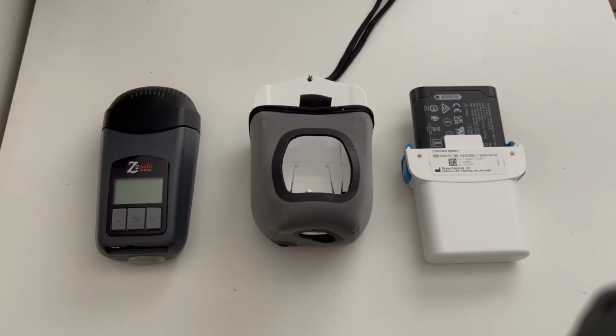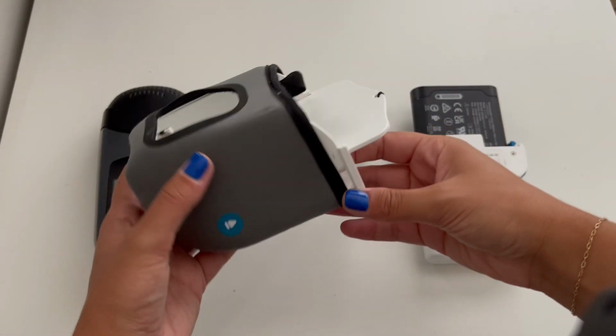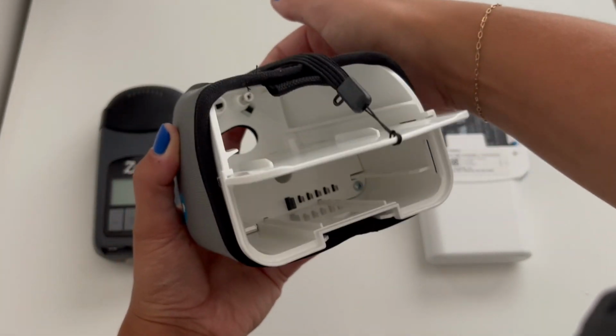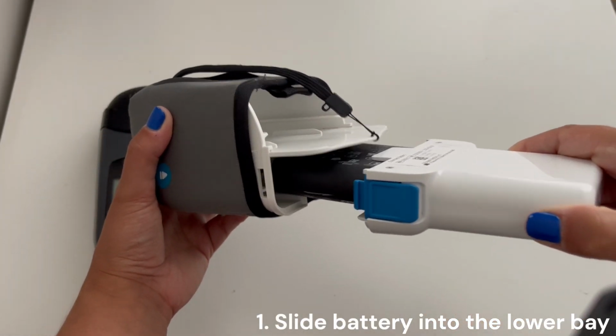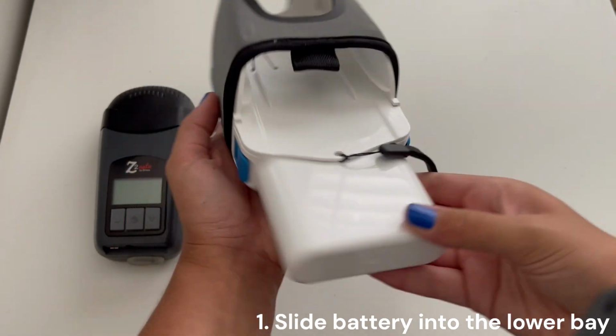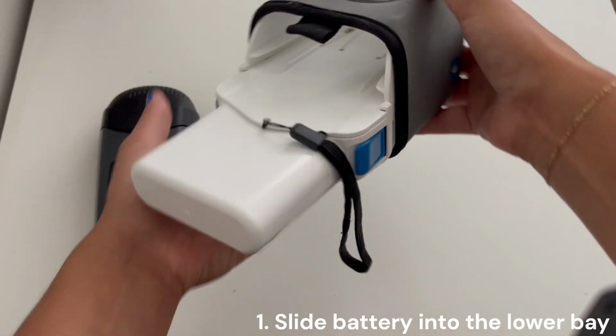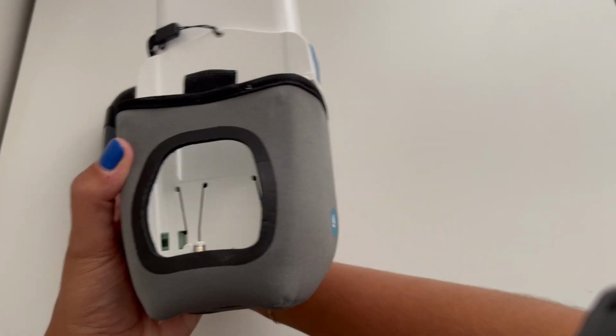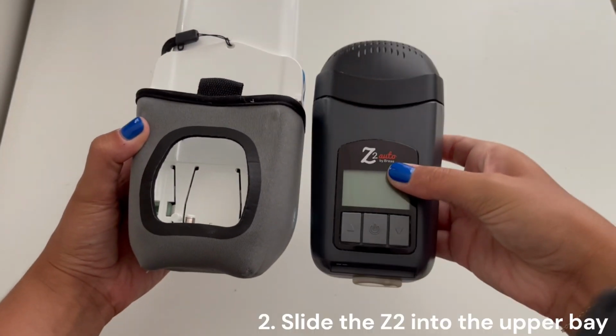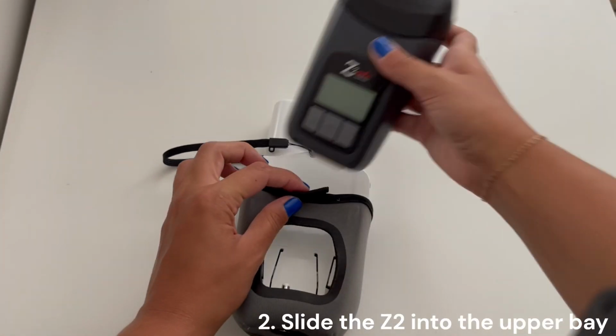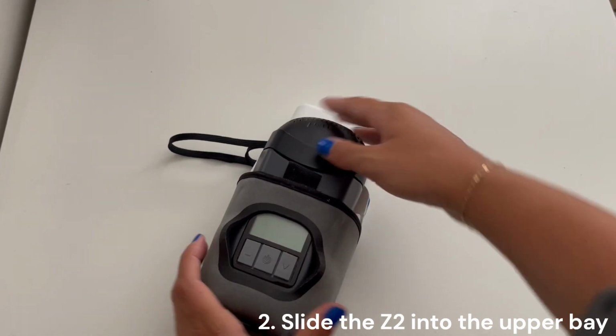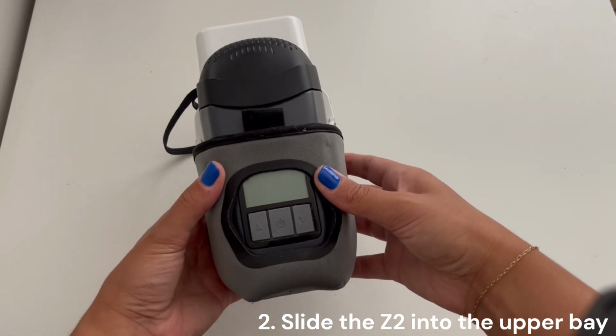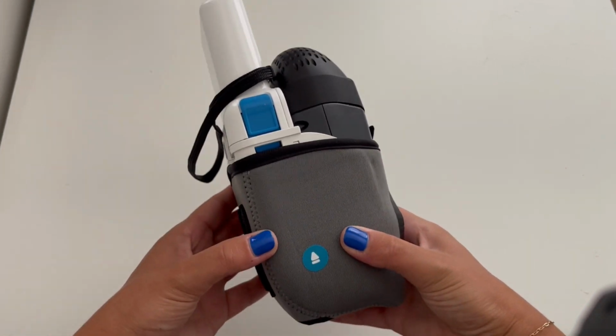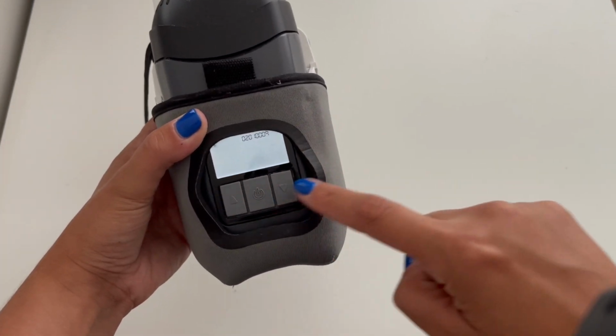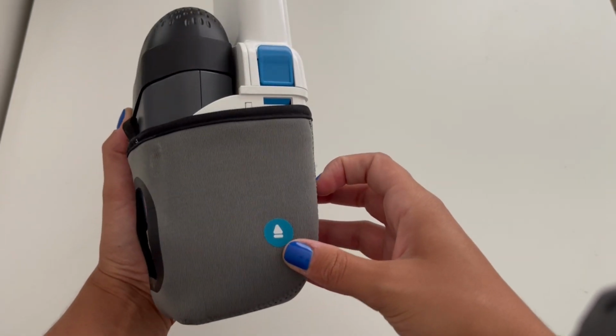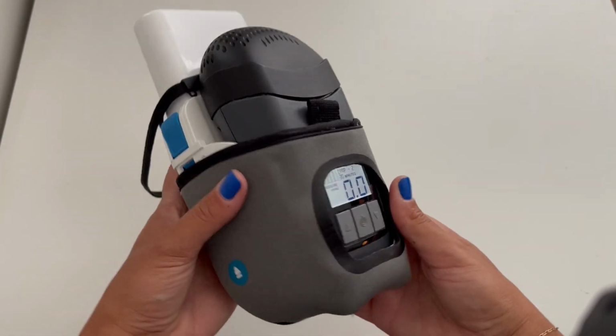To insert both the extended battery and your Z2 CPAP, first slide the battery into the lower bay of the Powershell. You will hear a soft click indicating the battery has locked into place. Then, slide the Z2 into the upper bay of the Powershell. You will hear another click indicating the machine has secured into place.